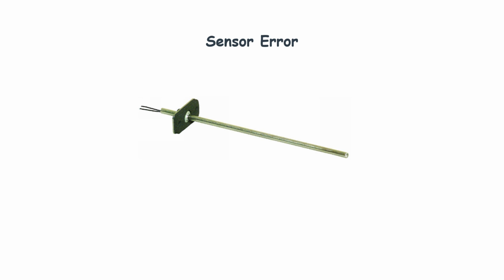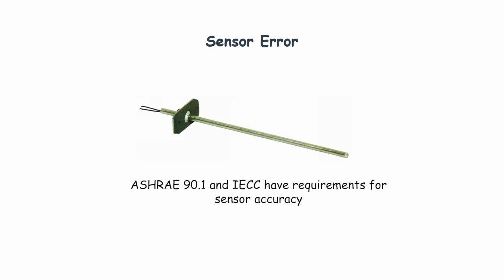One thing to keep in mind about different control methods is sensor accuracy. Complex control methods require multiple temperature and enthalpy sensors. Each of these sensors has error, and the sensors' combined error may result in poor performance of the economizer. Because of this issue, ASHRAE 90.1 has requirements for sensor accuracy which must be followed by all economizers.